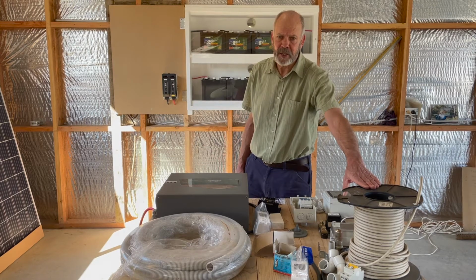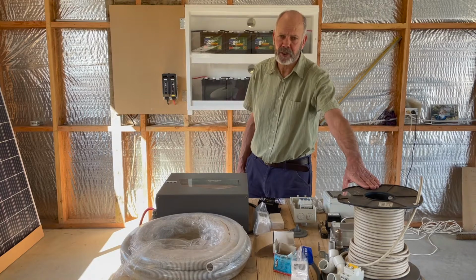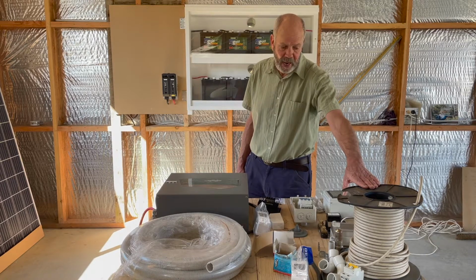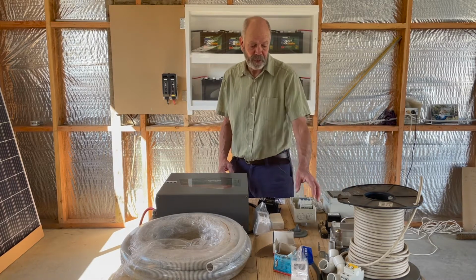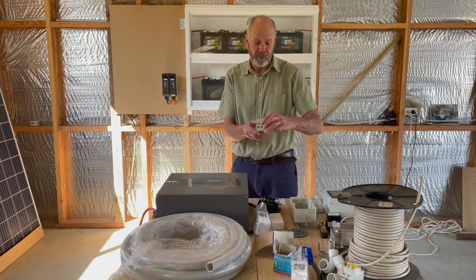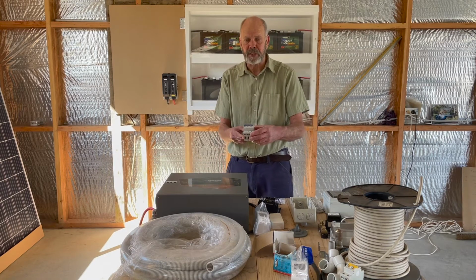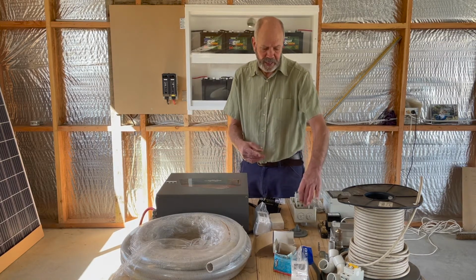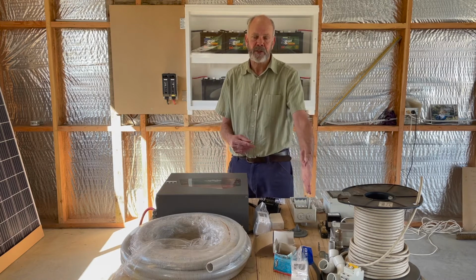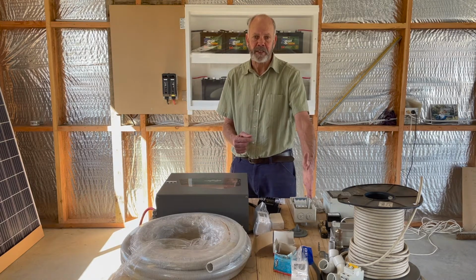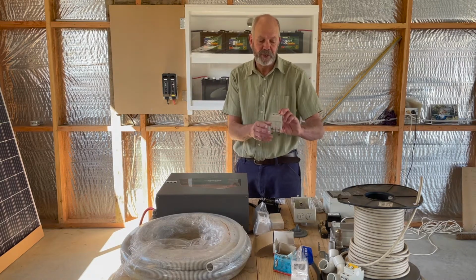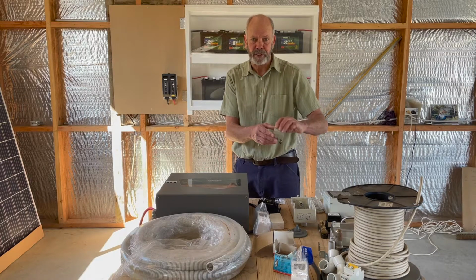In this case it's big enough to handle the current, but you can use a voltage drop calculator to determine the correct cable size for your array if you're using a bigger solar array or a longer run than I'm using. And this is going to go up through the 25mm conduit and into the bottom of this circuit breaker. At least the positive is going to go into the bottom of the circuit breaker. The negative is going to come up into the circuit breaker box and it's going to connect to the solar panel negatives. The solar panel positives will each go into the top of the circuit breaker.